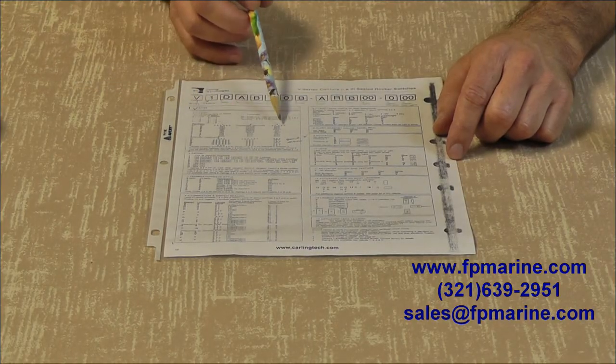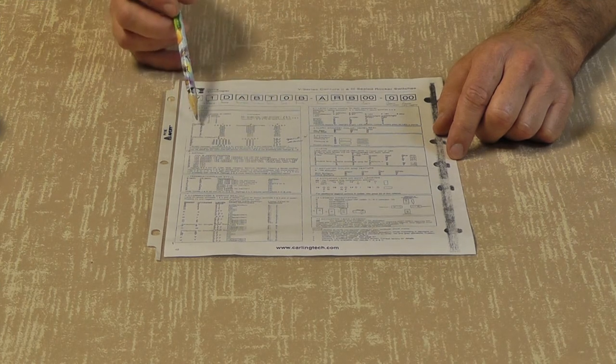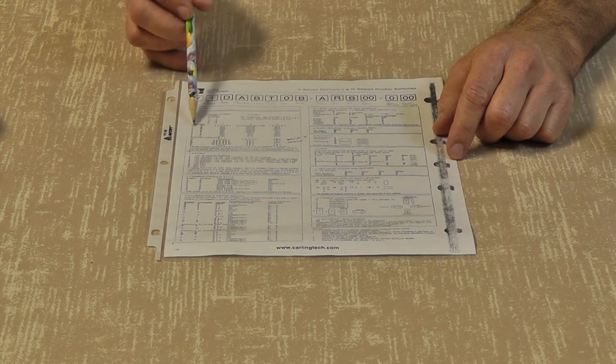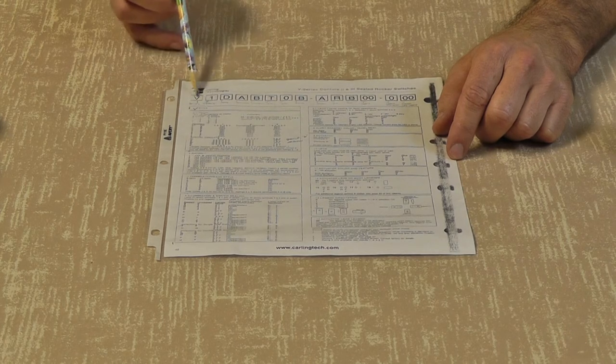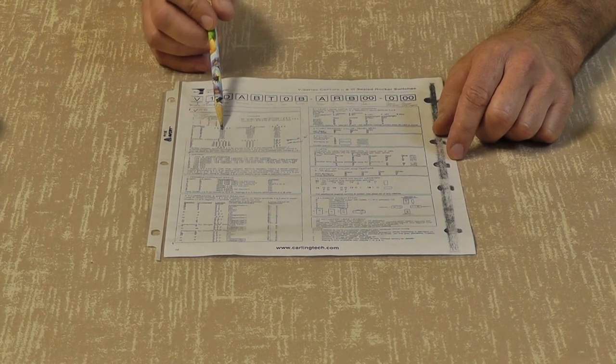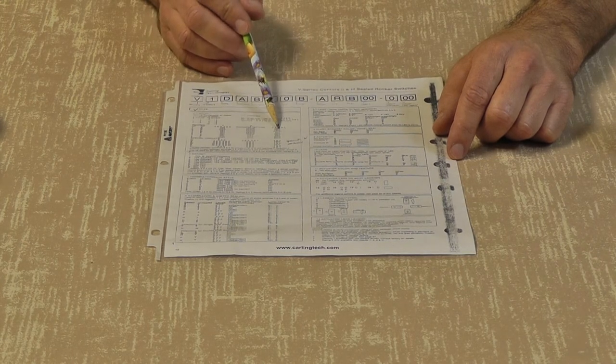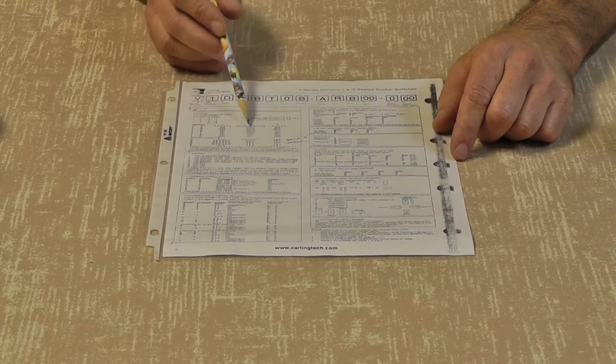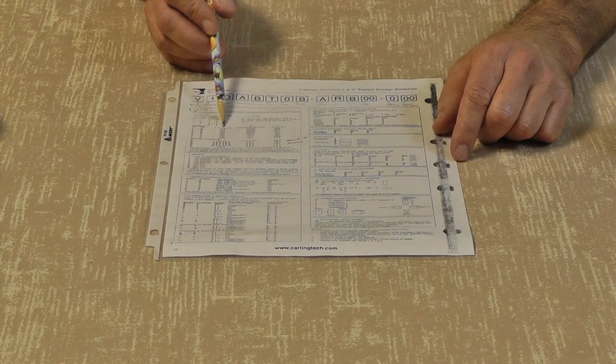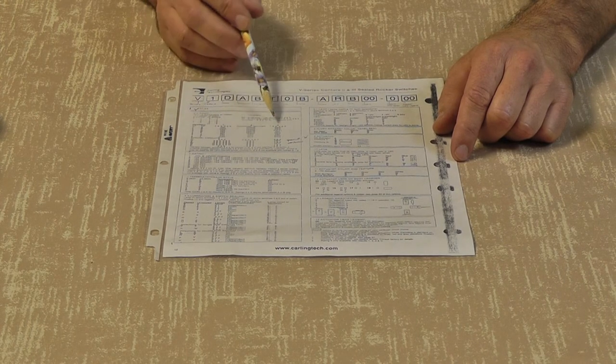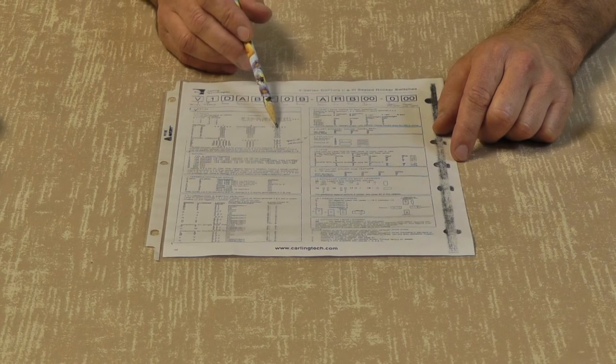To explain how this is worded here, each switch as you read across its row, like let's say it's a single pole switch, so it's going to be a V1. That's going to be an on, none, off. And as shown by the actuator positions, it doesn't have an actuator position number two. So when it's in actuator position number one, it's on. When it's in actuator position number three, it's off.